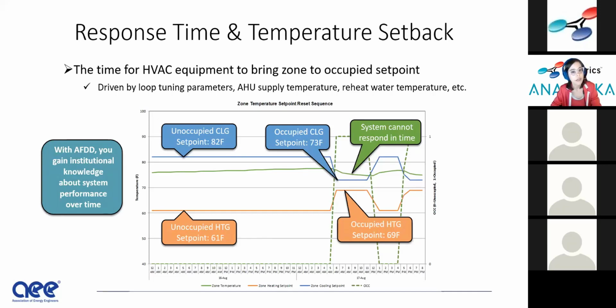Here, this example is response time. This is what I was talking about before, why air handlers sometimes are operating 24/7. This is more of an AFDD example, maybe not necessarily as predictive. But here you can see an unoccupied cooling set point of 82 and an unoccupied heating set point of 61. You can see that huge deadband between those set points.